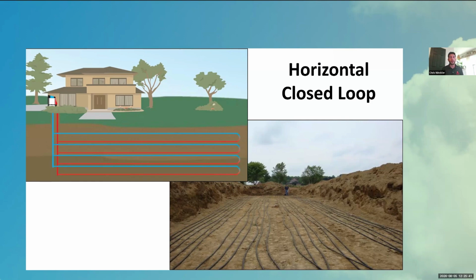Those are typically more in the 40-degree range, mostly because you get some benefit from simultaneous heating and cooling. As a residence pulls energy for heating, they're making the water colder. At the same time, a high-rise building, even in the middle of winter, might be air conditioning the majority of its top floors, so they're actually putting hot water into the loop. Because of that simultaneous heating and cooling, there's a lot of benefit, and it's easier to keep slightly warmer water temperatures, without going into too much detail.